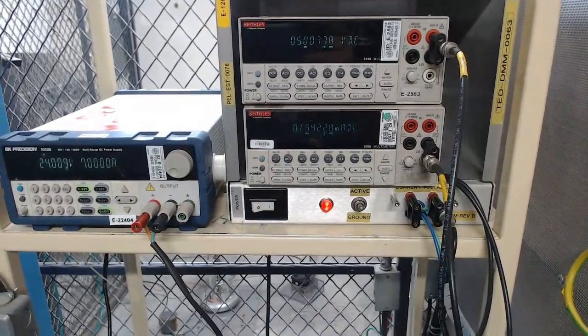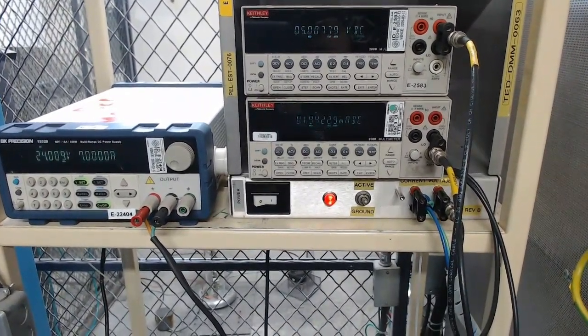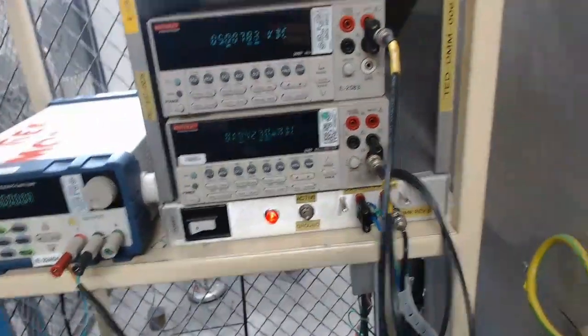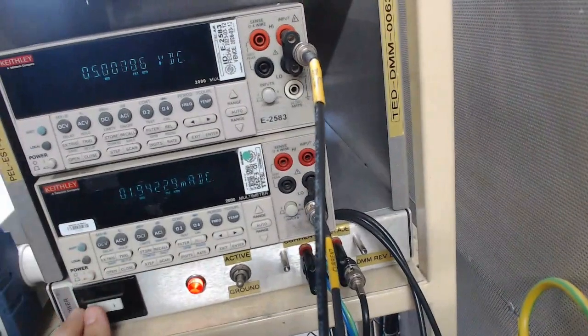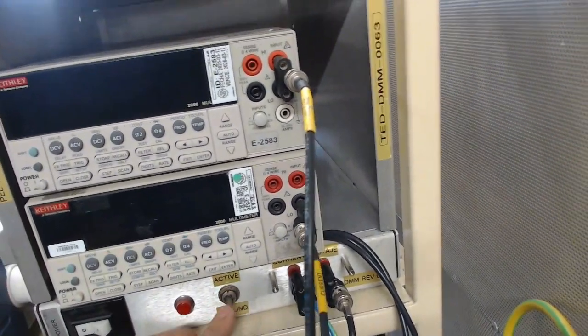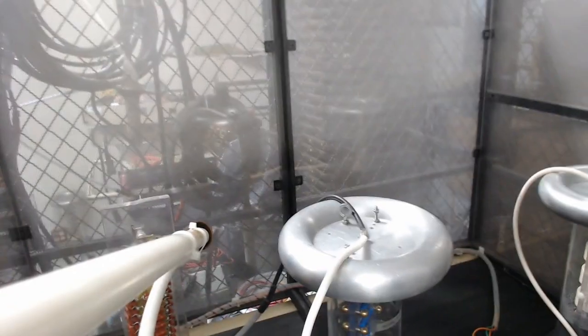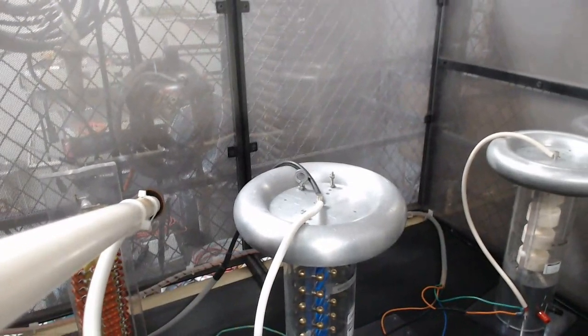Output voltage readings come from a 10,000 to 1 high voltage divider tap. Hence, 5 volts in this meter are representative of 50 kilovolts. We will proceed to engage the DMM box protection again and begin with the actual shorting of the output. We will approach the ground stick, which is an insulated rod connected to ground to the high voltage divider dome, performing 10 shorts to the output at a frequency of 1 short per second.